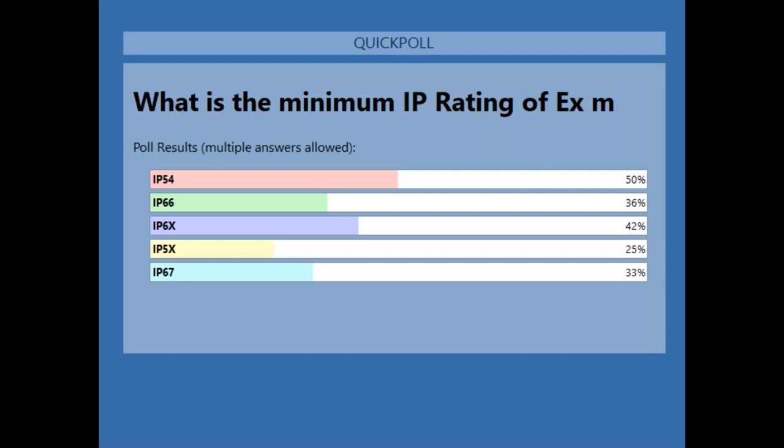So anybody who tells you you don't need an IP washer to maintain IP54 with 6 millimeters of threaded entry, you may want to read the standard and actually follow the certificate and follow the manufacturer's IOMs. So the minimum IP ratings for dusts, you can be looking at IP5X or 6X. And for gases, so GA, GB, GC, or underground mining, MA, MB, you'd be looking at IP54.